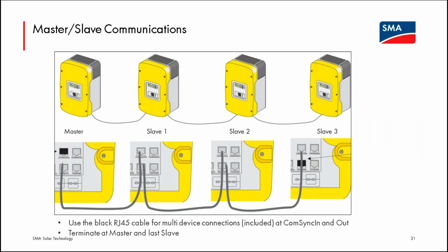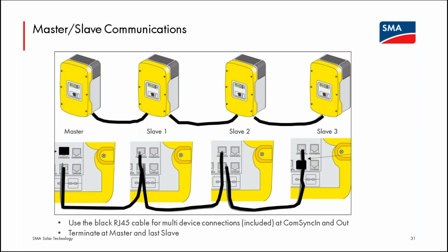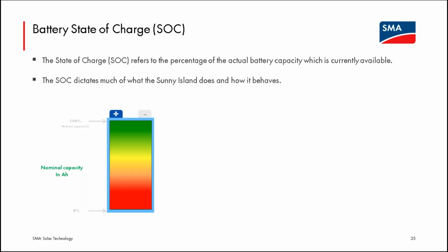All of that AC output synchronization is simply done by communications between the master and the slaves. And the black RJ45 cables that allow that are included in the box with every Sunny Island. So it's simply wiring those comms cables and programming at commissioning. Every Sunny Island out of the box is capable of being the master, and it's simply a programming choice.